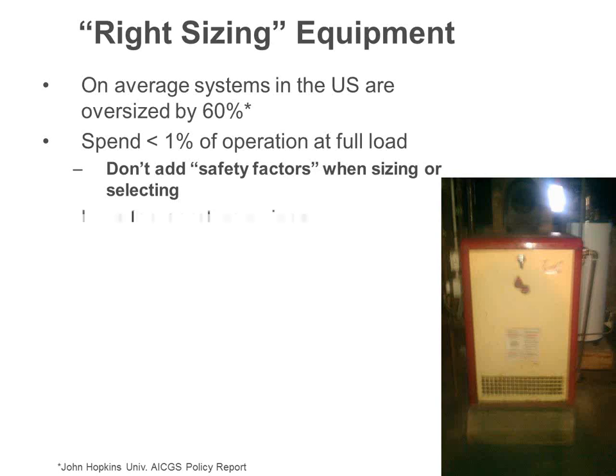Most people will say no, because it's not. It was oversized to begin with. So you went through the worst year and you never saw your boiler continually running. That means it's oversized to begin with right there. If you've got to prove it to them, when we go through how to size these boilers, pull the paperwork out. It's pretty easy to explain to them how you got this size.